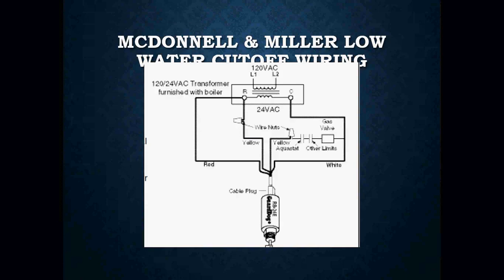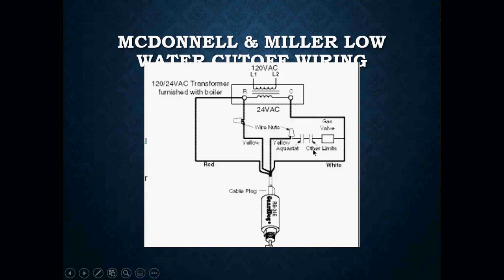Here's the wiring for your McDonnell Miller low water cutoff — usually they are powered with 24 volts. Your low water cutoff is wired in with your aquastat and your other limits on this particular burner. In this case, this is apparently a gas-fired boiler, so we will have other types of limits — first-out switches, high limit switches, flame detection devices, and all sorts of other safety devices wired in series with your low water cutoff and your aquastat.